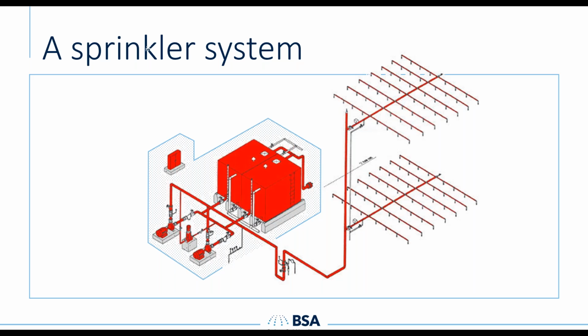Sprinkler systems are typified by similar things: a water supply, normally in the form of pumps and tanks for quite a lot of installations that we see here in the UK, although for domestic residential installations, that water supply may come in the form of public mains - just a pipe coming in from the main in the road into the building. There's a series of valves used to control the flow of water into the system. You may see some objects on the network of pipes, and these are to raise alarms, either responding to pressure or flow. And then the business end, which is an array of sprinkler heads. That pretty much typifies a lot of the sprinkler systems you would see out in the wild: a collection of pipes with pressurized water, sprinkler heads at one end, valves to control flow, and pressurized water coming from either the public mains or a pump and tank.